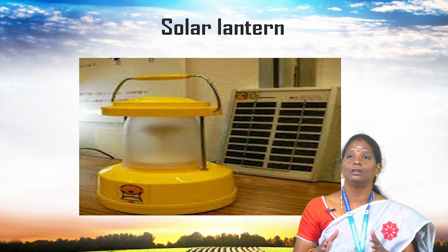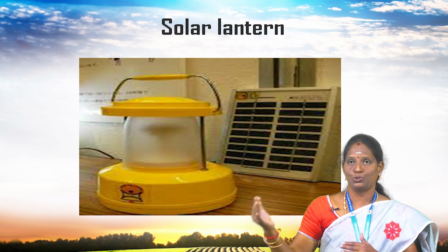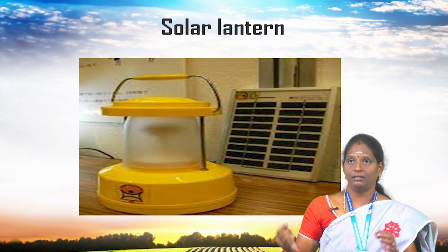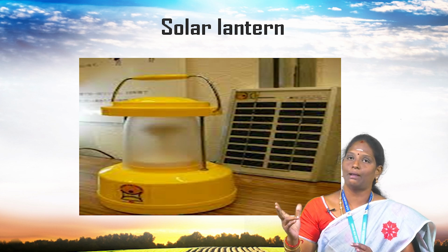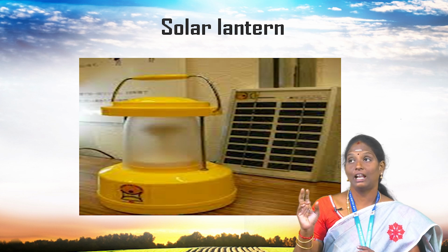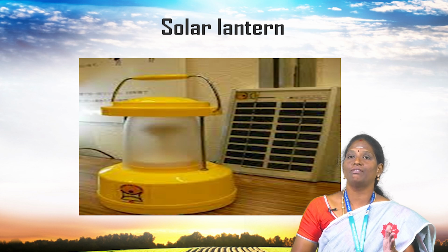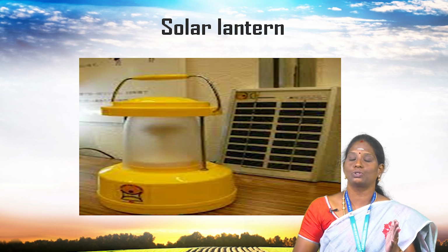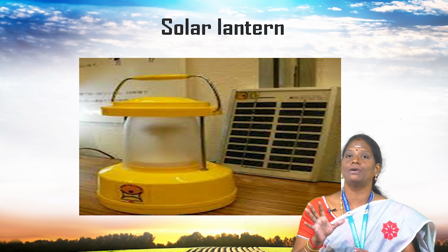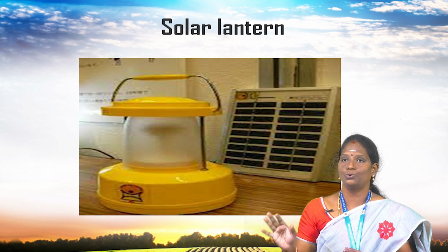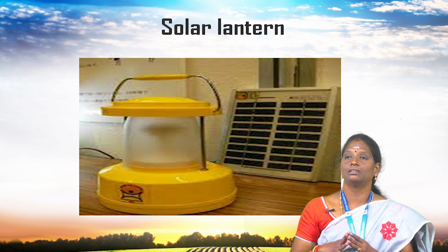During daytime, the module is placed under the sun and it is connected to the lantern through a cable. For charging, a typical lantern uses a 10-watt lamp. The expected life of the lamp is 3 to 5 years. Storage battery is one of the crucial components in solar lantern. Recombinant maintenance-free absorbed electrolyte batteries are being used. The battery has a life of 3 to 5 years.